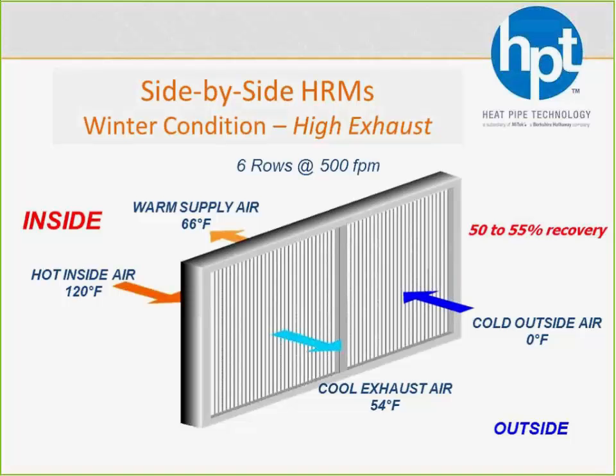In this case, I'm just going to look at where exhaust air is 120 degrees. So if it's 0 degrees outside, we're going to recover about 55% of those delta T's, so we would heat that outside air up to about 66 degrees or so. So let's say that 66 degrees is perfectly fine for heating that space. But that's, of course, with 0 degree air.